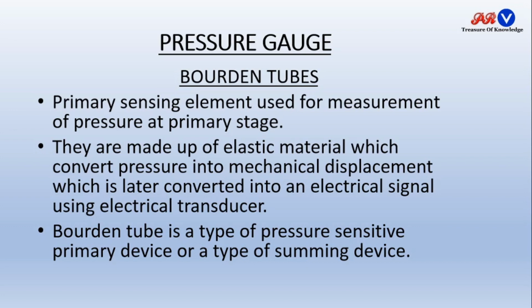Bourdon tube is a type of pressure sensitive primary device. So Bourdon tube is used for sensing the pressure. It is a primary device or a type of sensing device. So this is also known as sensing device, Bourdon tube.